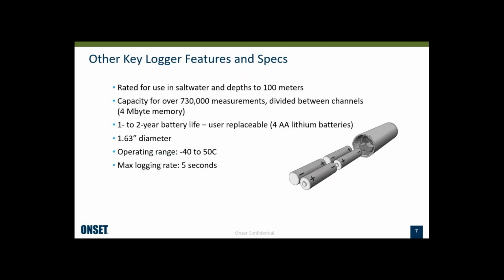So just some other highlights of the features. I show a little picture there of how the batteries can be changed. It just means removing the end cap of the logger to change the batteries and slide them in. Capacity is roughly 730,000 measurements, and that's divided by the number of channels that the user decides to log. You know, I told you all the different measurements that can be recorded. They don't have to log all of those because that can use up the memory pretty fast if they're logging every single parameter. They can if they want, but they just have to be aware of the memory impact.